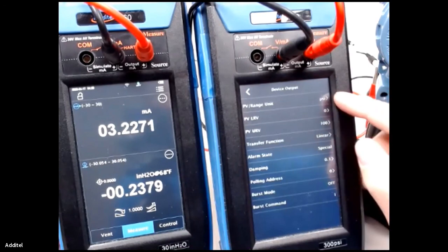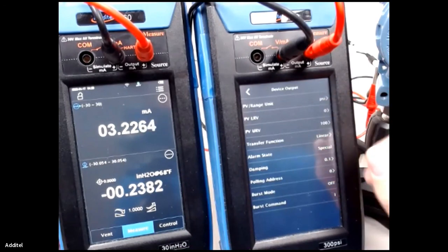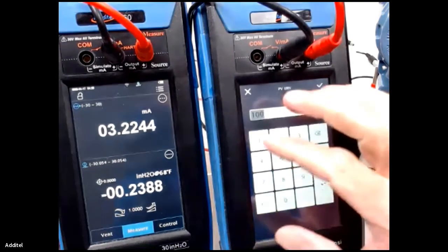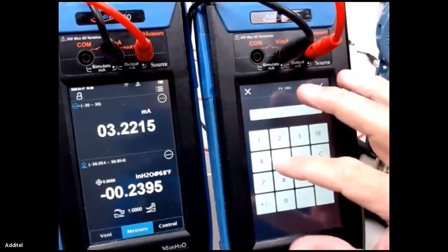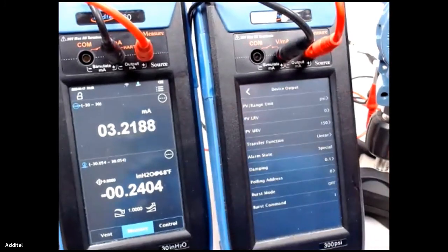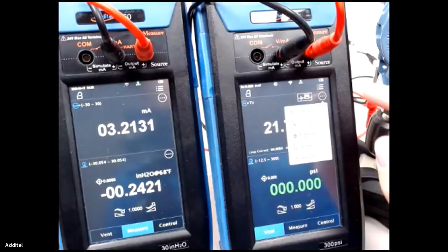Right now it's set to PSI 0 to 100. Let's go ahead and change that. Let's change it to 150 and hit enter. We just literally adjusted this HART transmitter with the 760. I think that's a really cool feature that if you want to go out and make some changes to your HART transmitter, you can do it with this unit.